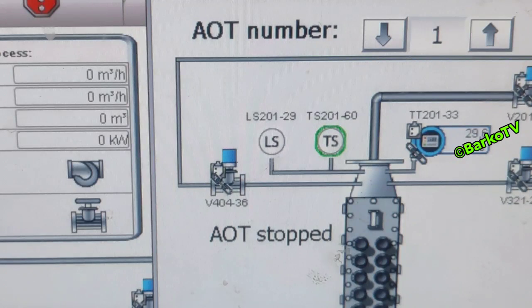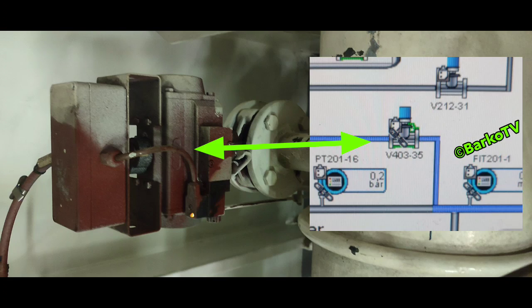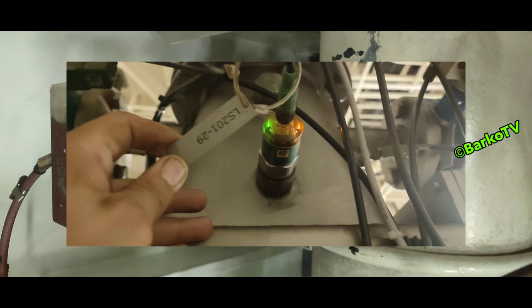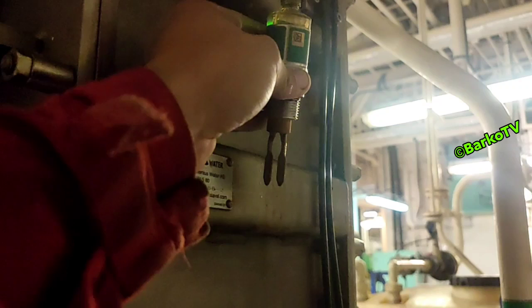This is the status indicator for the LS: when it lights up, it means it detects the water. Confirmed that the two level sensors are okay. The suspected valve in actual status is open, and we also have an indicator on the level sensor showing that water is detected — the AOT is filled because the indicator is lit.